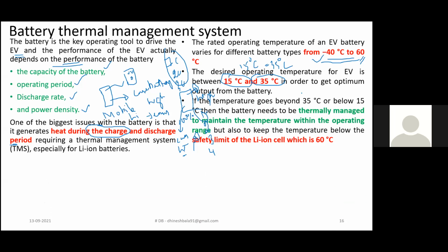If the temperature goes beyond 35 degrees Celsius, or if the temperature falls below 15 degrees Celsius, you need to thermally manage the system. So we are very much clear that your battery is able to operate between the temperature range of minus 40 to 60. But the optimal temperature limit is that it should be able to run in the temperature zone of between 15 to 35. So what actually happens when it rises above 35 or falls below 15?